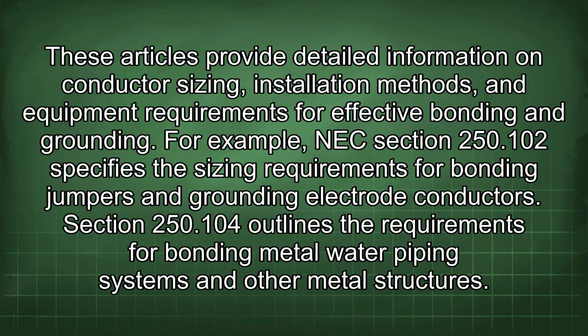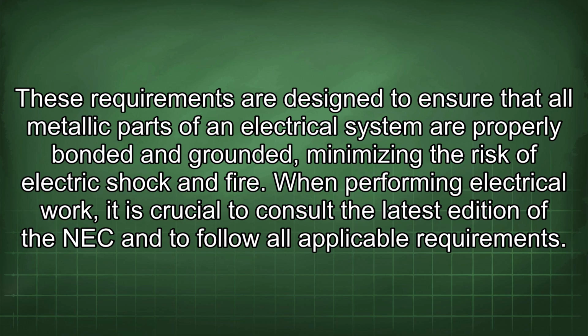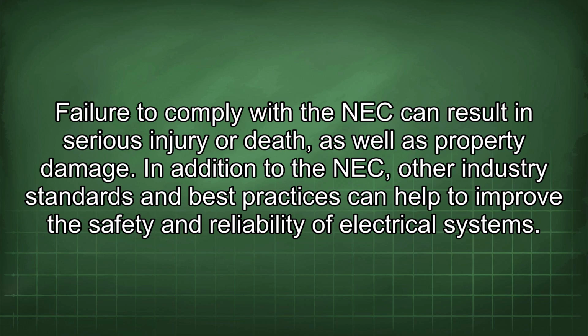For example, NEC Section 250.102 specifies the sizing requirements for bonding jumpers and grounding electrode conductors. Section 250.104 outlines the requirements for bonding metal water piping systems and other metal structures. These requirements are designed to ensure that all metallic parts of an electrical system are properly bonded and grounded, minimizing the risk of electric shock and fire. When performing electrical work, it is crucial to consult the latest edition of the NEC and to follow all applicable requirements. Failure to comply with the NEC can result in serious injury or death, as well as property damage.